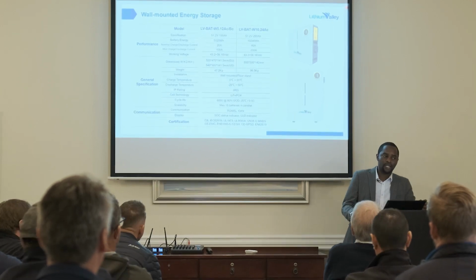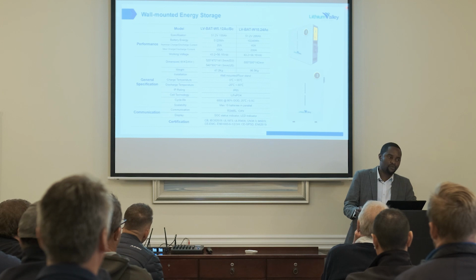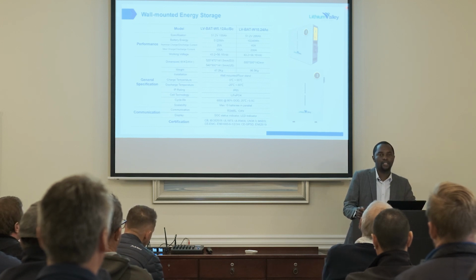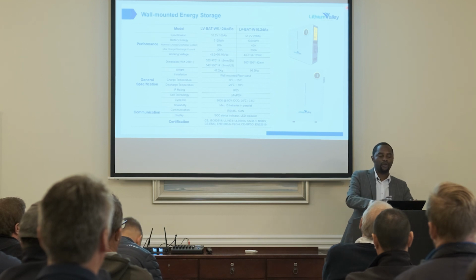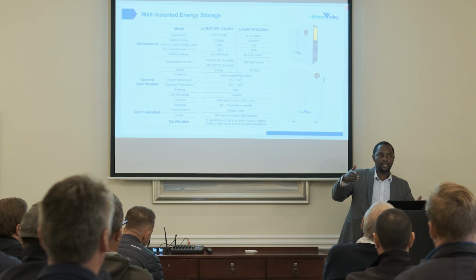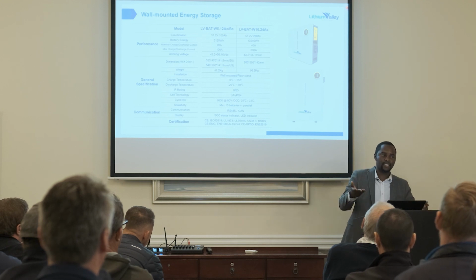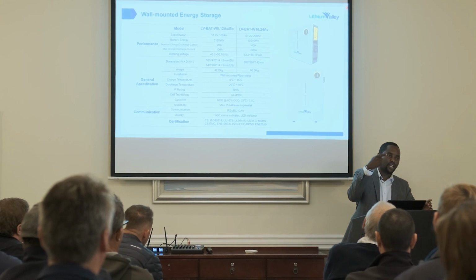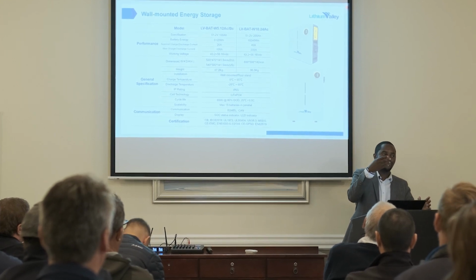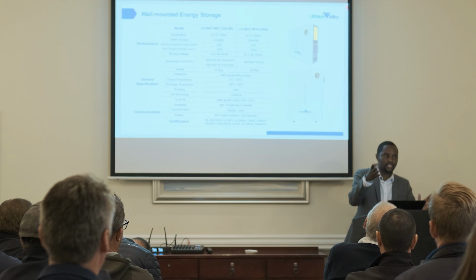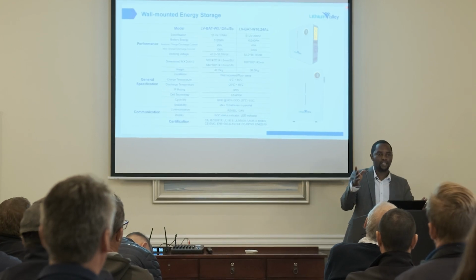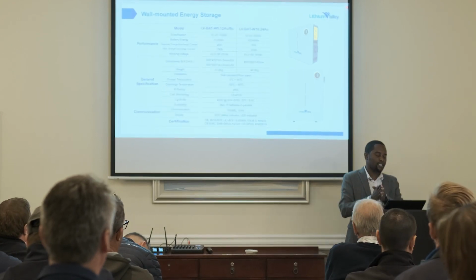Another advantage, whereas maybe on the Samsung batteries, you are still limited to 8, but this can go up to 15. You don't have any dip switches. It does the auto addressing. Remember, when you've got batteries in parallel, each battery should have its own unique name, which is the Modbus ID, that the BMS can call and say, okay, battery number 5, what is your charge current? Battery number 5, what is your temperature? Battery number 6, it calls them individually. It can't just be one Modbus ID.